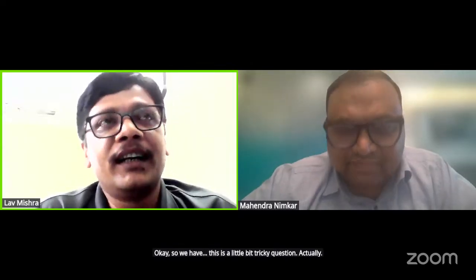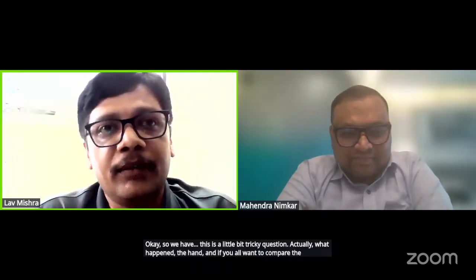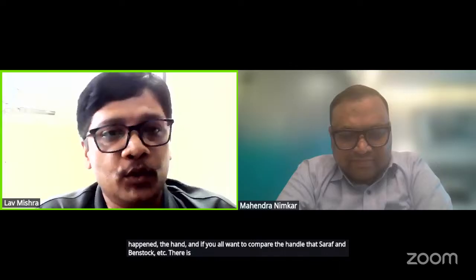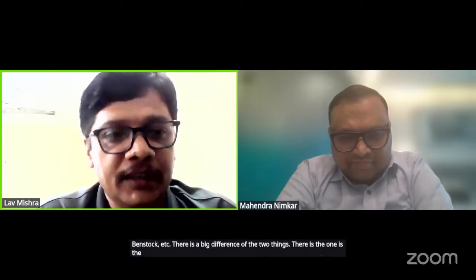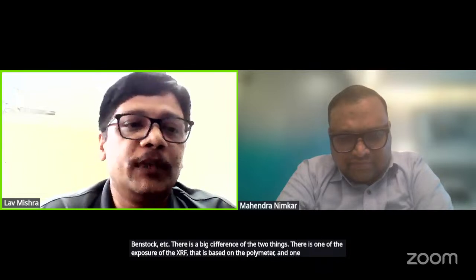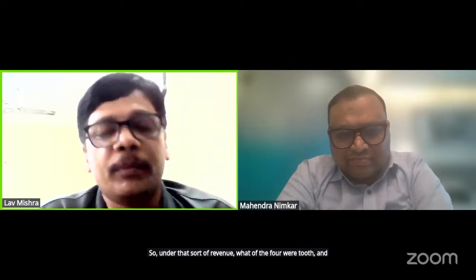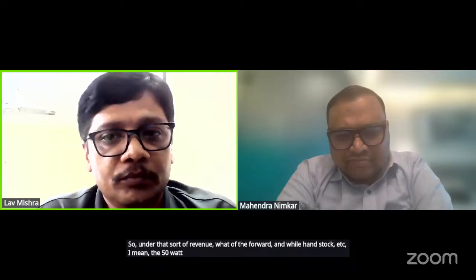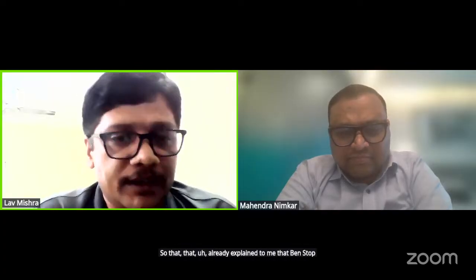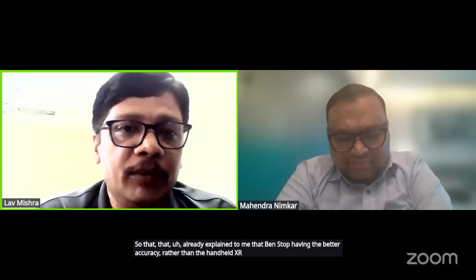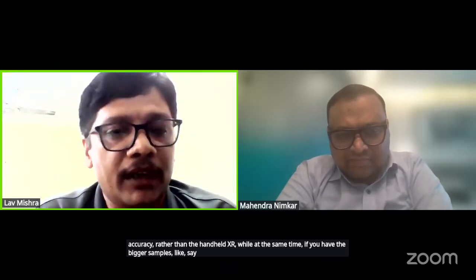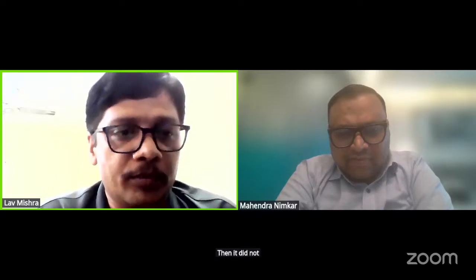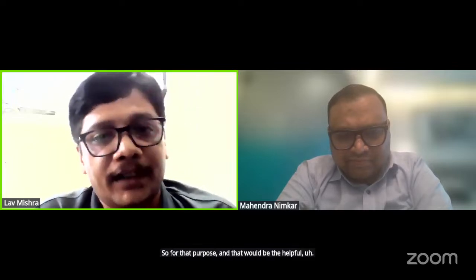If you want to compare handheld XRF and benchtop XRF, there is a big difference between the two. One is the exposure of the XRF that is based on the collimator, and the other is the wattage of the X-ray tube. Handheld XRF has a 4-watt tube, while the benchtop XRF has a 50-watt tube. That already explains that benchtop has better accuracy than handheld XRF. At the same time, if you have bigger samples, like big panels, it is not quite possible with the benchtop. For that purpose, handheld would be the helpful instrument.